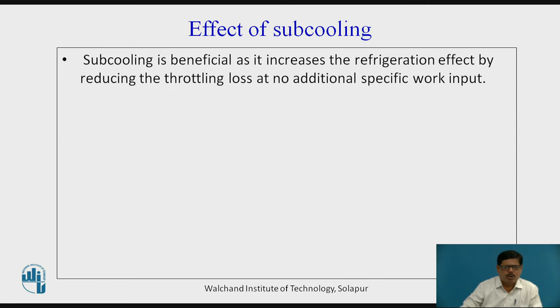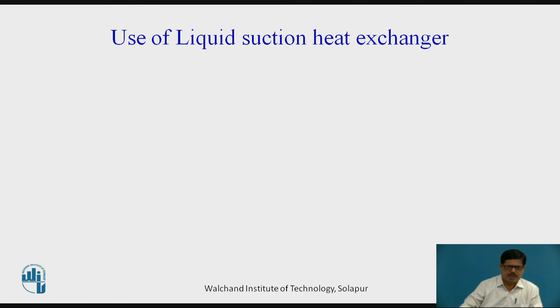Subcooling is beneficial as it increases the refrigerating effect by reducing the throttling loss without any additional specific work input. Subcooling ensures only liquid enters the throttling device, leading to efficient operation. Therefore, when we use subcooling, the COP will always increase.